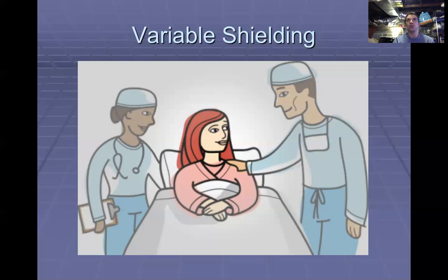Once we've seen 1,000 or so patients, we have a pretty good idea of the range of shielding that a wide variety of patients will provide, and you can build some conservatism into that, but ultimately it lets you get away with a little bit more than what the regulations outright say.